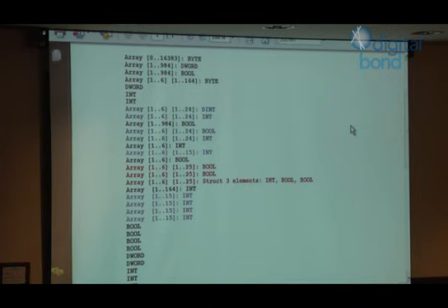So we know that this attack is operating on 6 cascades. And we see something else here. For example, we have this structure with 24 entries. This fooled us for several weeks because we thought it would have a relation to the plant configuration, but it doesn't. It's just a memory table that's used for indexing into another address table where I/O addresses are stored. But this is important here.